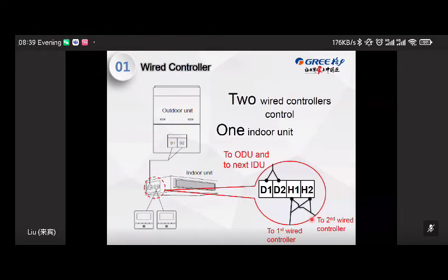However, you can also use the other wiring method, such as double controllers controlling one indoor unit. In this case, one controller should be the master, right? Another one should be the slave, right? So if there are two masters, the units will show the CP error code. If double slave, will also cause communication error. So one master and one slave wired controller. That's the correct setting by the P13.